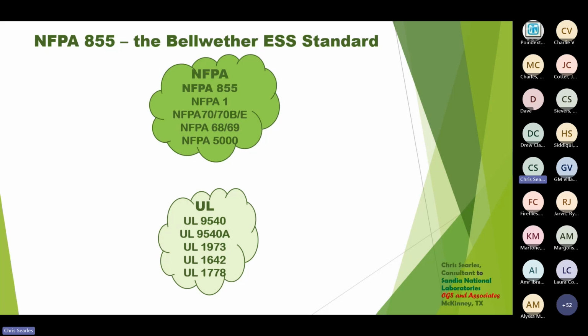9540A is not a standard, a guide, or even a testing requirement. It's considered a document, perhaps a guide, that leads anybody wanting the UL 9540 certification through a hazard mitigation analysis compliance testing, showing that your energy storage system—and it is a system document—will not spread a fire, and now explosion, beyond the confines of the unit, module, or rack that the system is contained in.